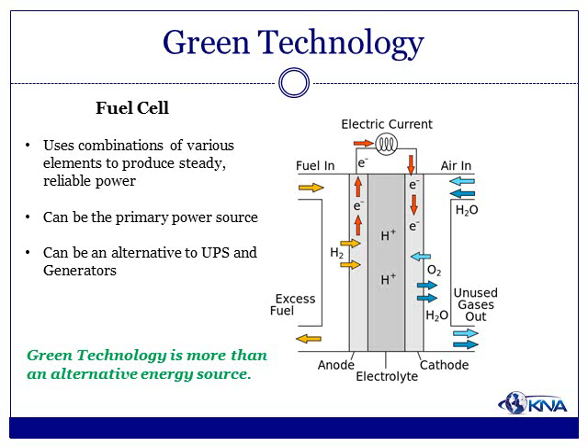The fuel cell is the newest of these technologies, most typically using combinations of natural gas, hydrogen, water, or oxygen to produce a steady, reliable power source. It is changing the way data centers are designed. Recently, very high-profile technology companies have built large data centers incorporating fuel cells as their primary power source, leaving the power grid as the backup source. Not only is this configuration reducing demand on the power grid, but it can also be an alternative to uninterruptible power supplies and fossil fuel-driven generators.